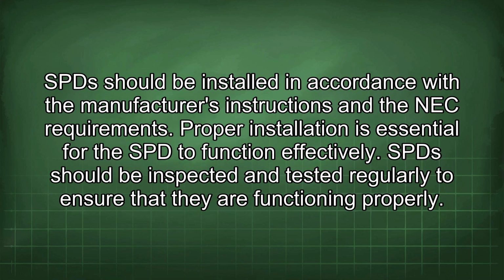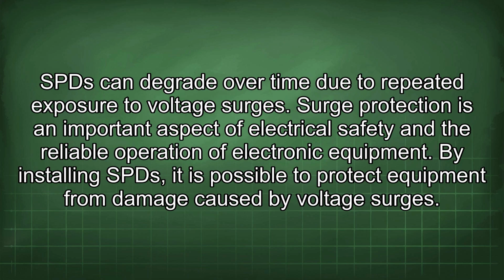SPDs should be installed in accordance with the manufacturer's instructions and the NEC requirements. Proper installation is essential for the SPD to function effectively. SPDs should be inspected and tested regularly to ensure that they are functioning properly. SPDs can degrade over time due to repeated exposure to voltage surges. Surge protection is an important aspect of electrical safety and the reliable operation of electronic equipment.